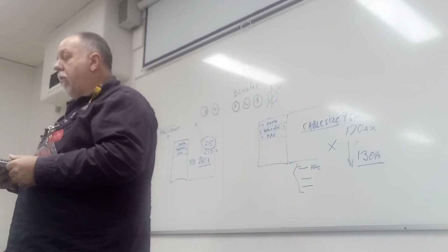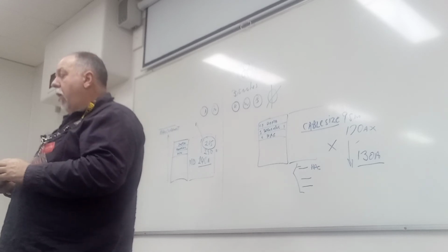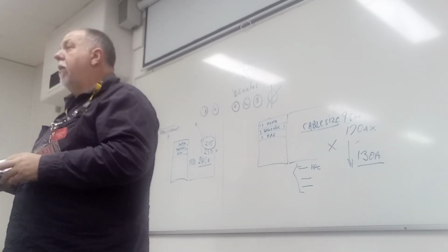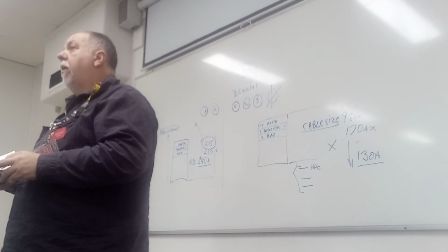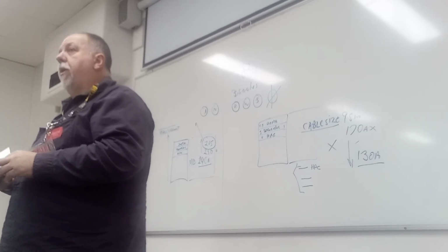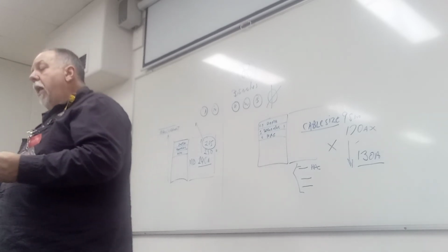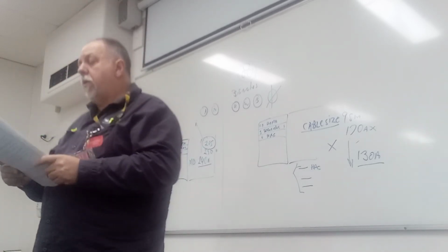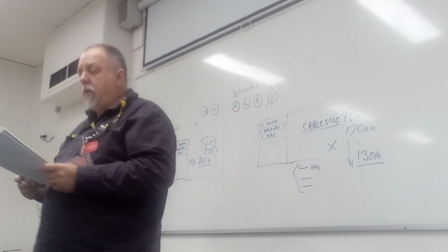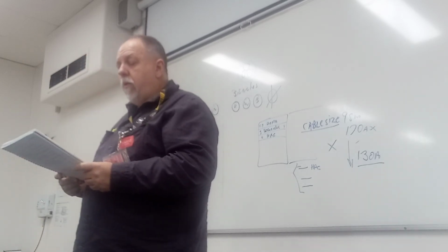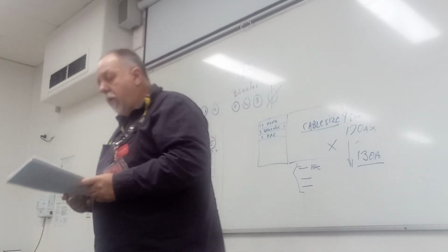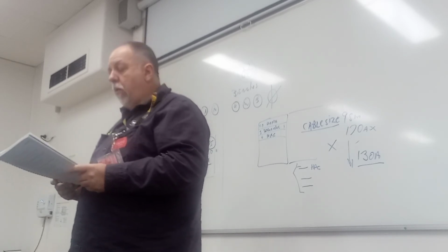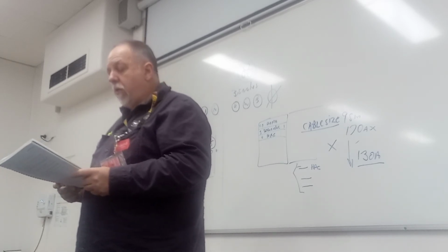Do we all see that, yes or no? In column 2 there, it's got up to 50, and then above 50 to 300, that is talking cable size, not current. All right, I get some people thinking that's amps. The last one, table 29, talks about resistivity. Resistivity of the soil, all right, 1.2 is a common value that we see in the questions, which doesn't apply a derating at all. So that has a 1 factor across the top there.